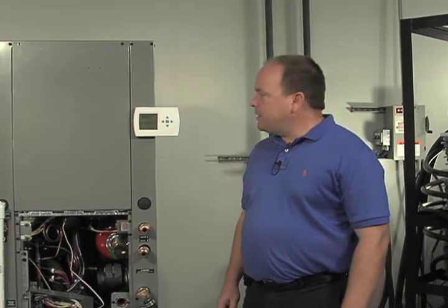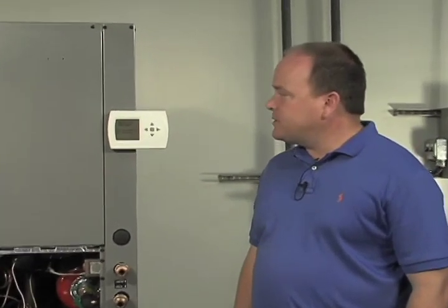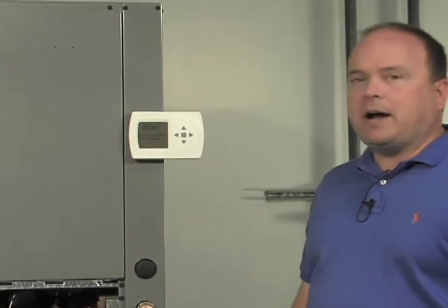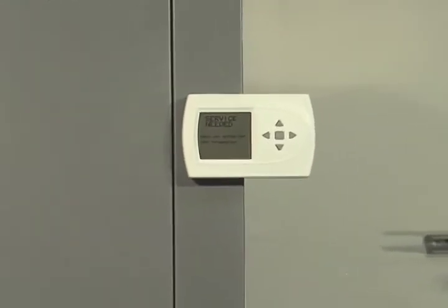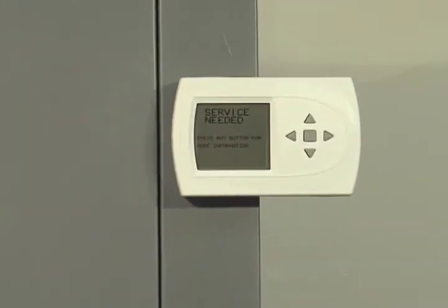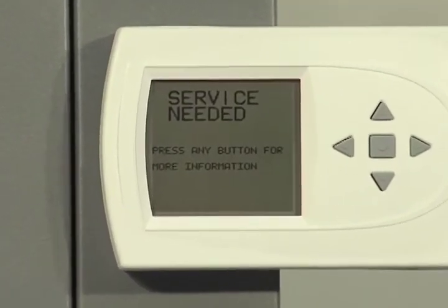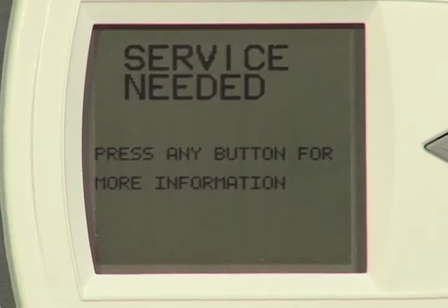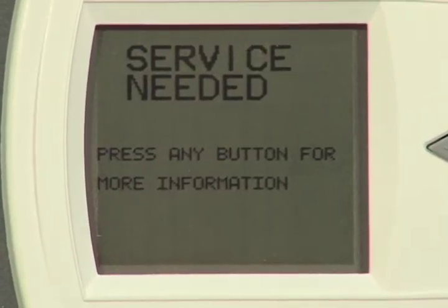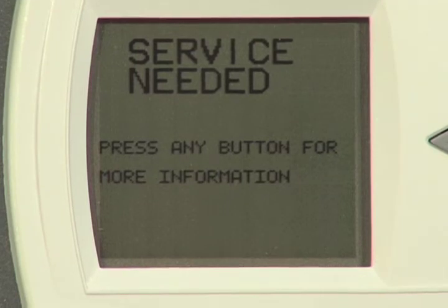We're going to show you another fault condition here again. This is another hard lockout fault. This is a Code 3, which is a low pressure switch fault, but that low pressure switch is actually on the high side of the system, so we actually utilize it as a loss of charge switch.